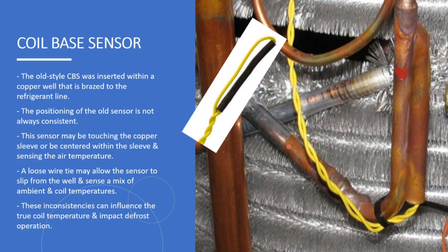This is the older version of the coil sensor, where it was pushed into a tube connected to the bottom circuit of the coil. So a few things were issues with these. Sometimes they would fall out and you would have to put a tie wrap here so it wouldn't fall out. Sometimes it was touching this edge, sometimes it was touching this edge of the tube, and sometimes it was in the middle, not touching any edges. So again, there was some inconsistencies there.